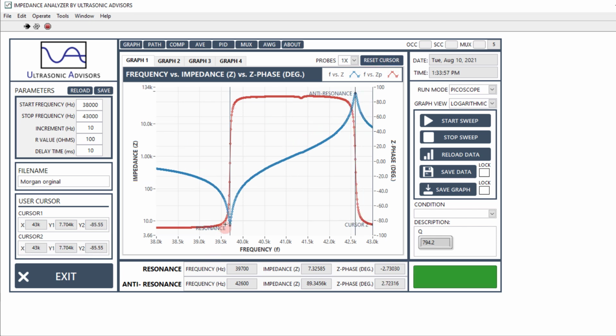in measurement. So you need to be careful in understanding if you're measuring your transducer properly, if there's not something wrong with how you're holding it, how it's being positioned, as we saw from the piezo crystal. Depending on if you don't hold it exactly at the center, which is the nodal point, you're going to significantly alter the response, and it can be to the point where you cannot interpret the values any longer. Here we would have incorrectly measured the quality factor, although probably during actual operation it wouldn't have mattered as much.